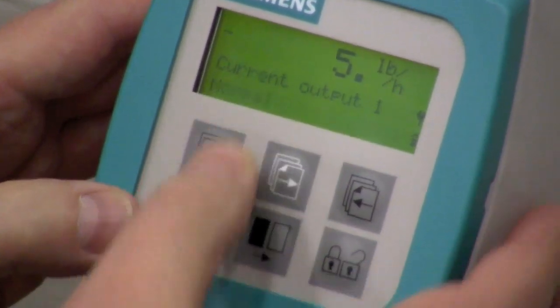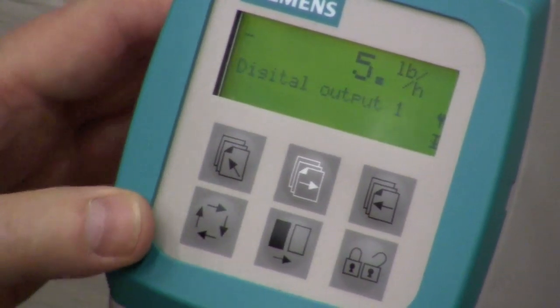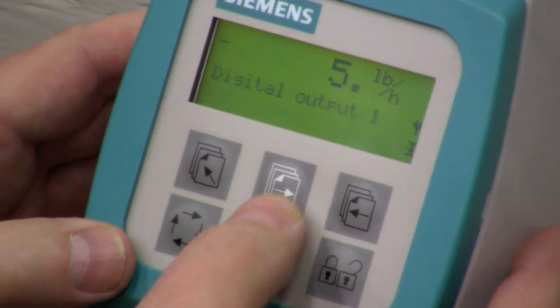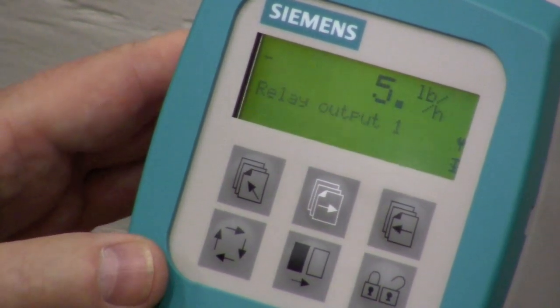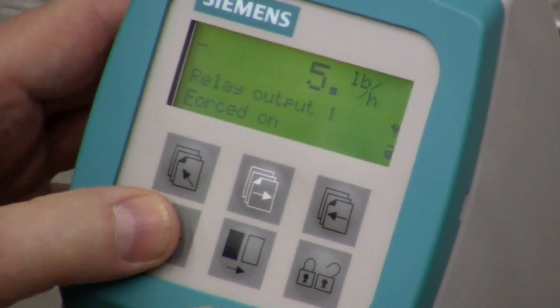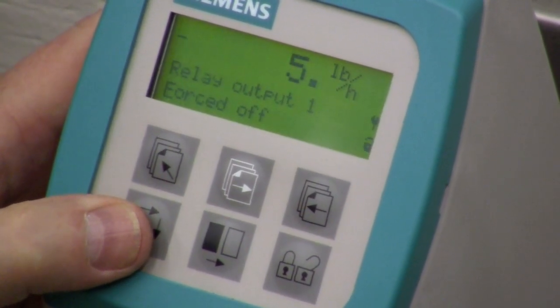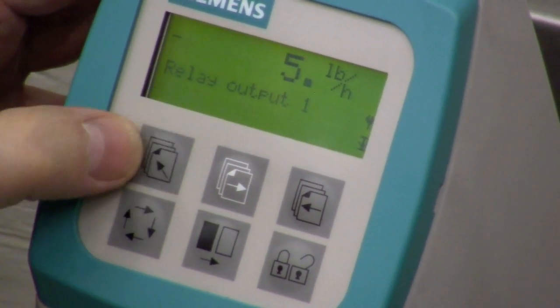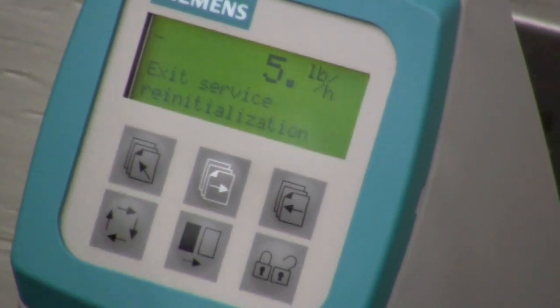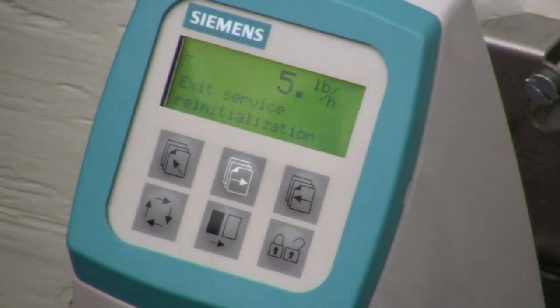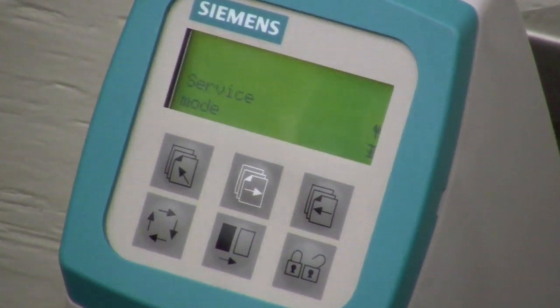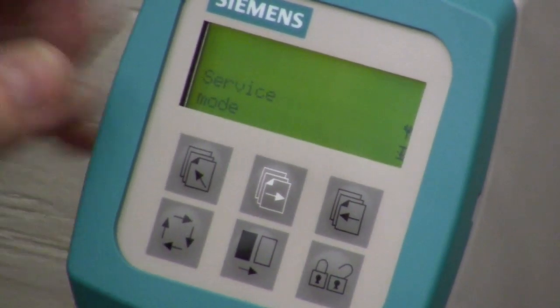As well as the current output, there's a digital output. You can get into it — it's set for normal — and you can change it to force that digital output on or off. We'll stay at normal mode. And there's a relay output as well; you can unlock it, force it on or force it off. That's another good way of testing what's happening downstream and making sure everything is connected properly. When you exit service mode, it reinitializes the entire device to make sure it's all set up properly, and anything you changed in service mode will not affect your initial configuration.